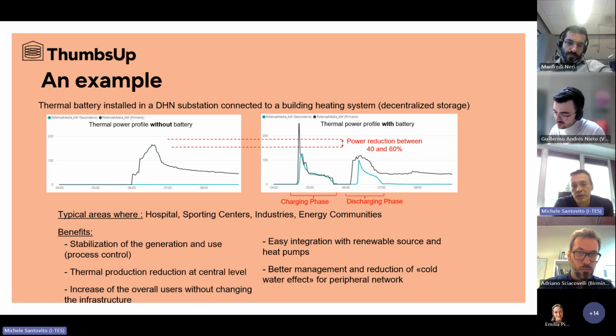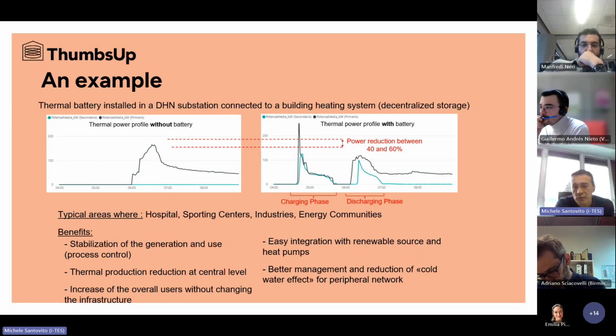With the batteries, during the night when there are very low requests from the field to the central power, we charge the batteries. So the curve you've seen from before 5 to half past 5, we charged the battery and then used the charge to reduce the peak. In this case, the dotted lines are not aligned, but I hope that's clear — this cuts the peak that we saw without the battery.